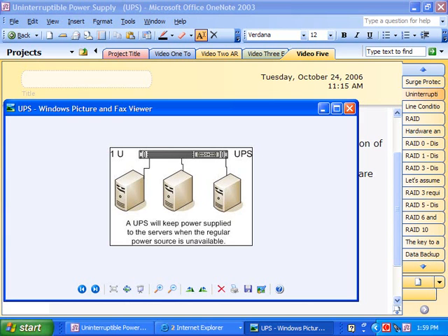And there are a couple of factors that determine how long those devices are going to get power, because occasionally network admins act like, well, I got a UPS, so when it kicks over, I don't have to worry about it. Well, you still have to worry about it if the power doesn't come back on immediately, because the length of time the UPS will keep these devices powered up depends on two major factors. The first is the number of devices connected to it, because the battery in the UPS only has so much power, and if 6 devices are draining power from it, obviously it's going to be a lot faster than if you just have 2 devices connected. The other key is the capacity of the battery itself.